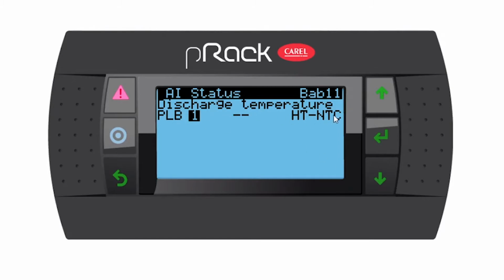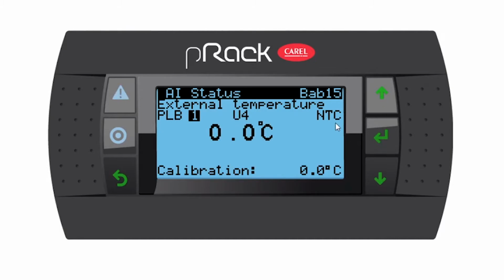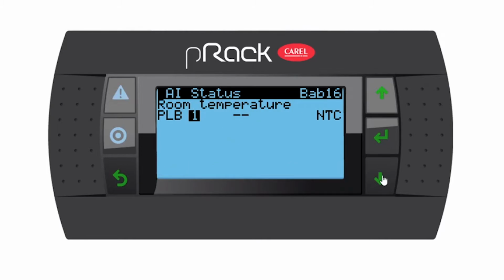Discharge temperature, but this is discharge temperature for the whole rack, so no, because remember we have one per compressor, so we're not going to assign this one. Do you have liquid temperature? Yes, if you do, you can assign it. External temperature. Yes, we do have external. I'm going to make it U4, and it's a normal Carel NTC with 0 calibration. Perfect. Let's go down. Do you have a room temperature? No, we don't. Discharge pressure.